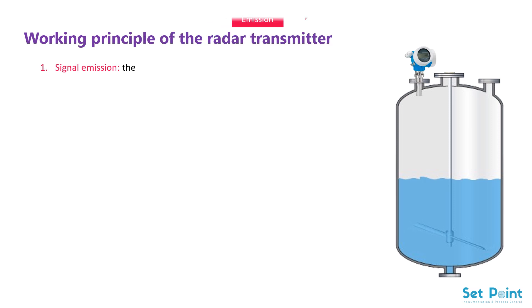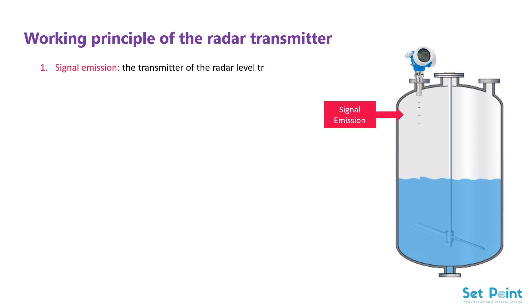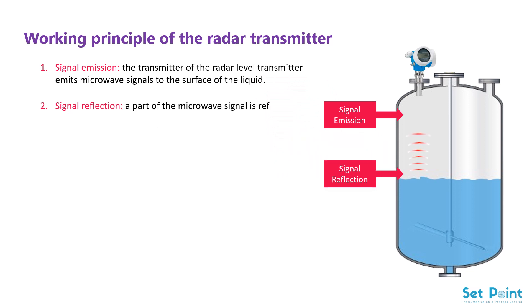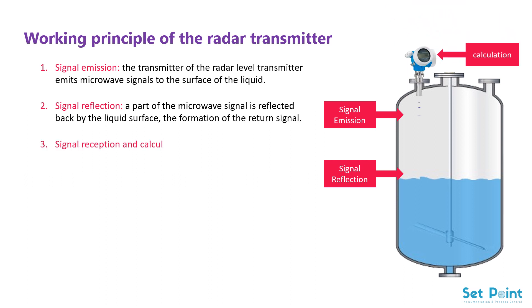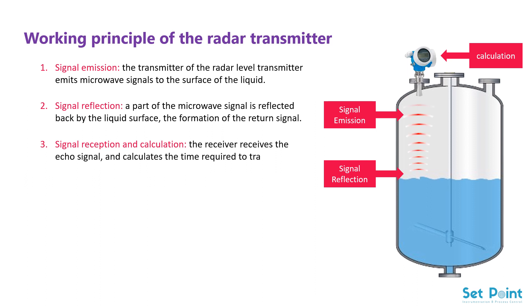Working principle of the radar transmitter. Signal emission: the transmitter emits microwave signals to the surface of the liquid. Signal reflection: a part of the microwave signal is reflected back by the liquid surface, forming a return signal. Signal reception and calculation: the receiver receives the echo signal and calculates the time required for the signal to travel and return.